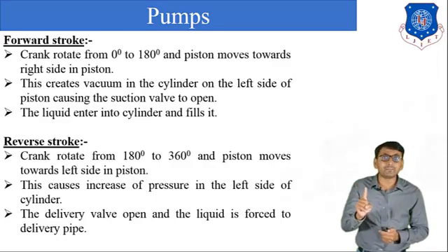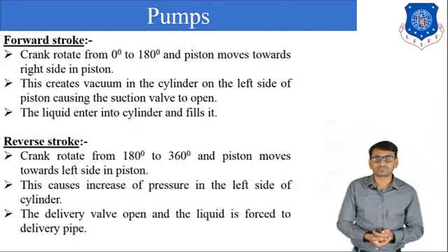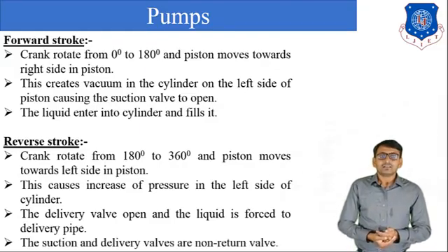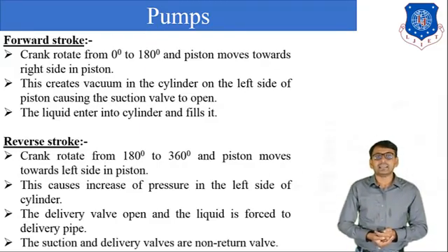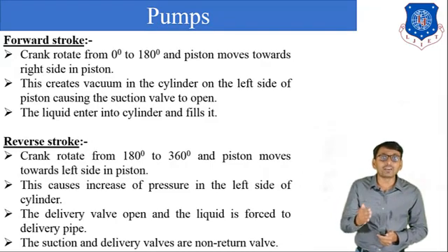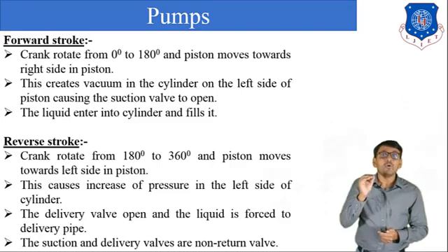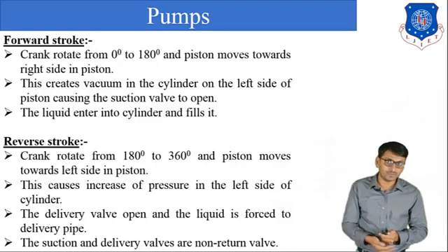One cycle is completed in two strokes. The forward stroke is also called the suction stroke, and the reverse stroke is also called the discharge stroke. The suction and delivery valves are non-return valves, and these two valves are operated only due to pressure difference.